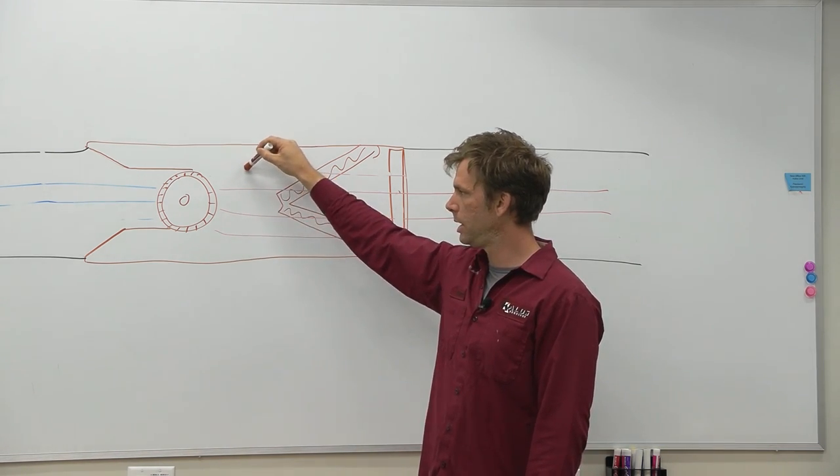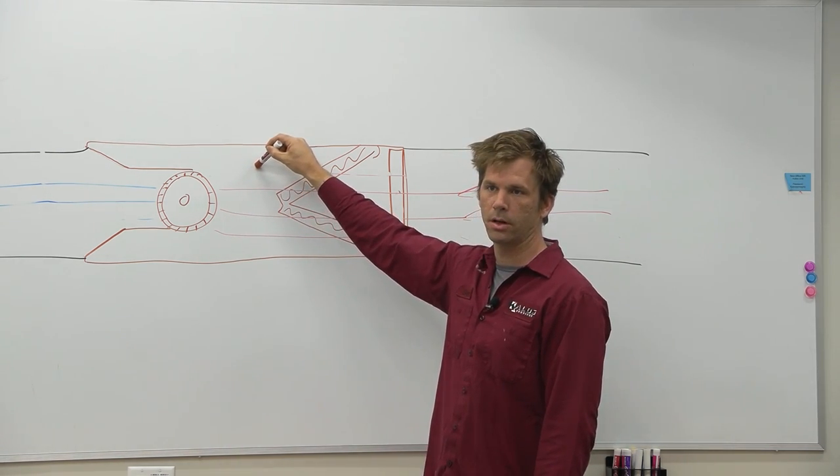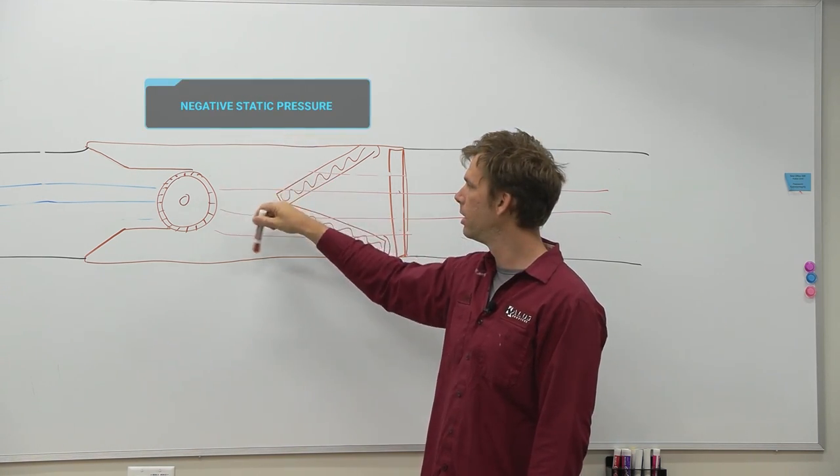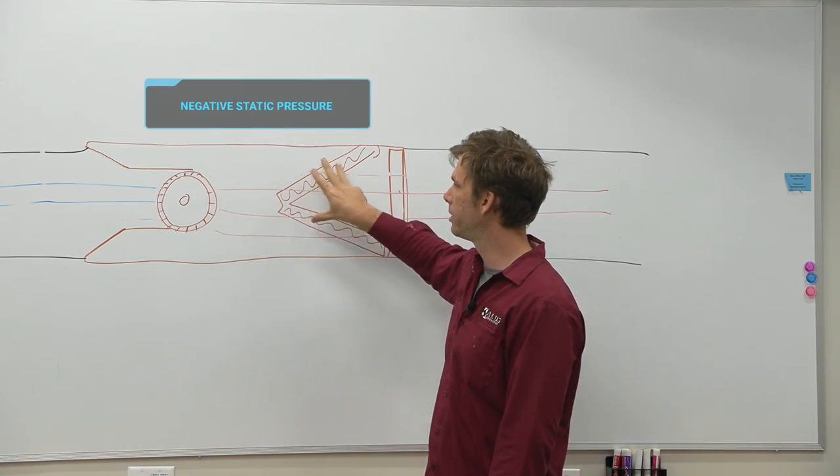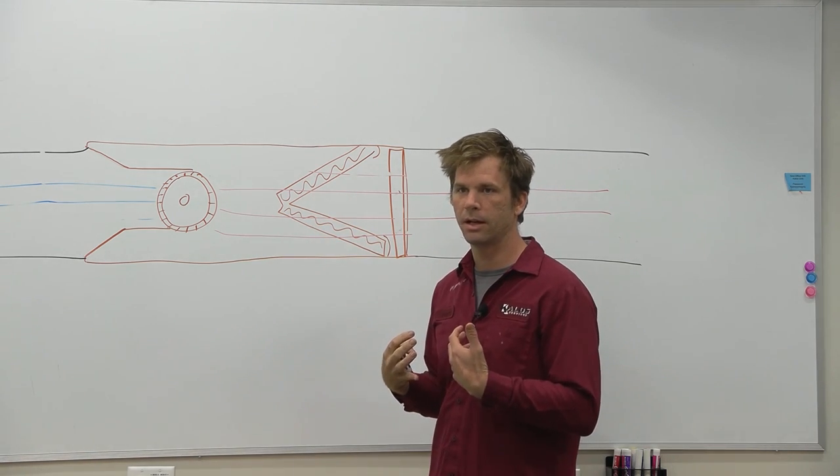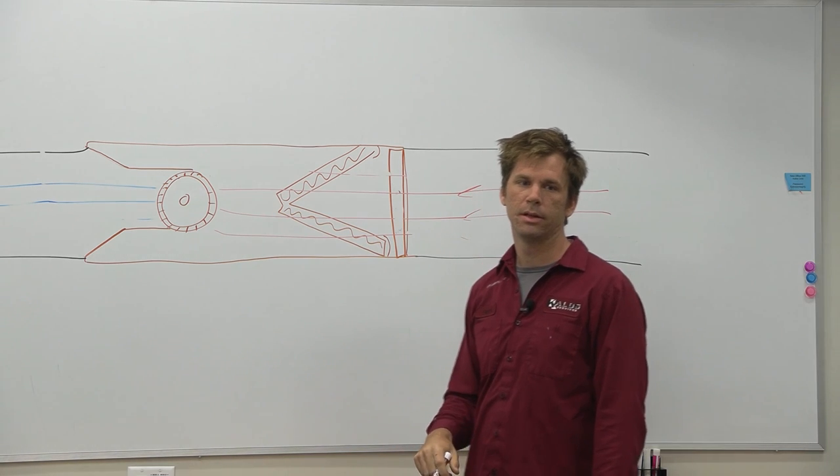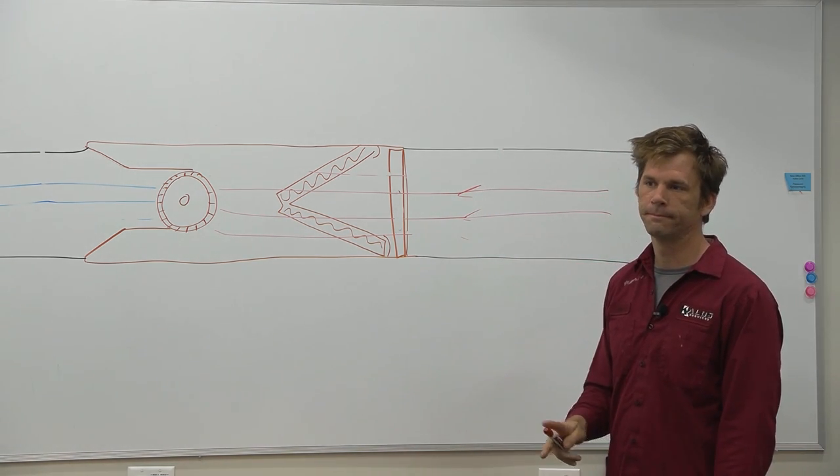We're going to have a big drop across our coil. In here, there's going to be a much stronger vacuum. We'll have a negative static pressure in here above the coil. The blower's trying to pull, it's not getting a lot of airflow through there. It'll be a much stronger pull here than if your coil's clean.